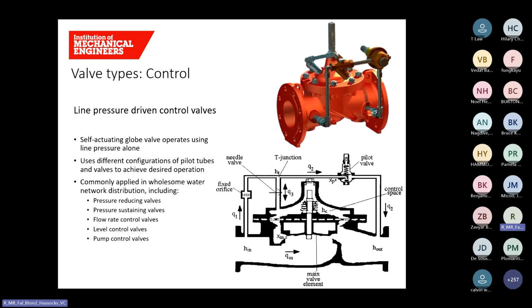On to control valves. The only one we'll cover today is the line pressure driven control valve. So these are self-actuated valves, and they use the pressure of the fluid flowing through the pipeline to regulate system parameters like flow or pressure. You don't need any external power or actuators. The valve automatically adjusts in response to changes in the upstream or downstream pressure. These are ideal for remote or energy independent installations.